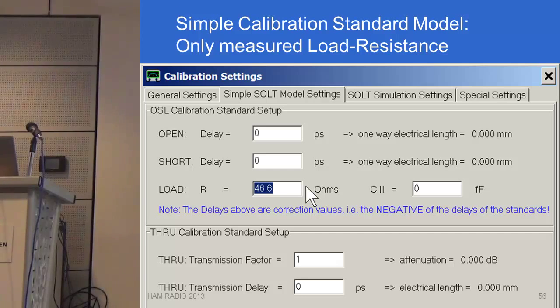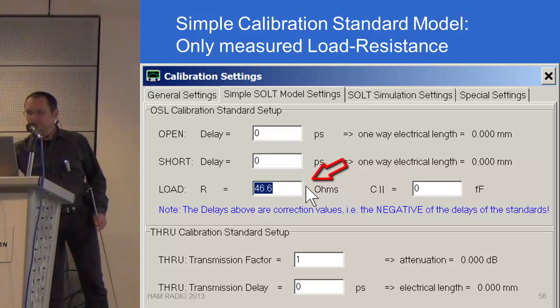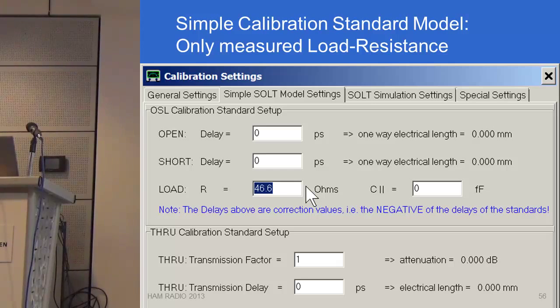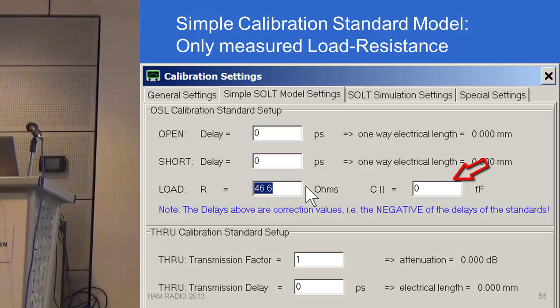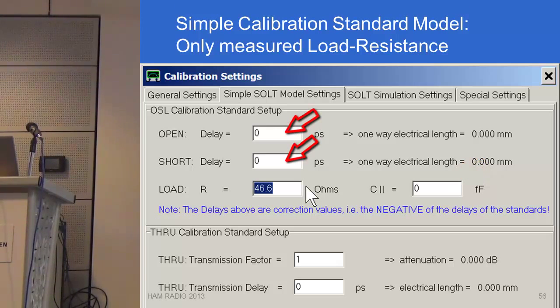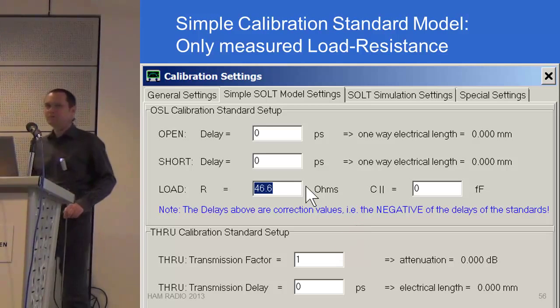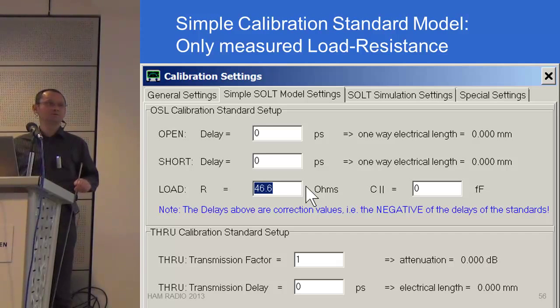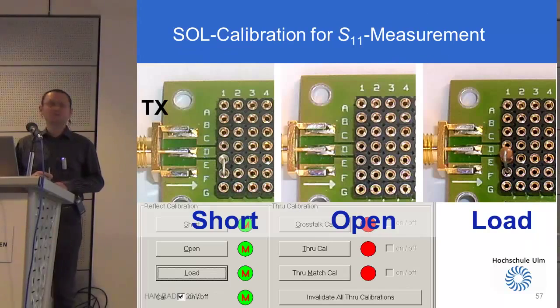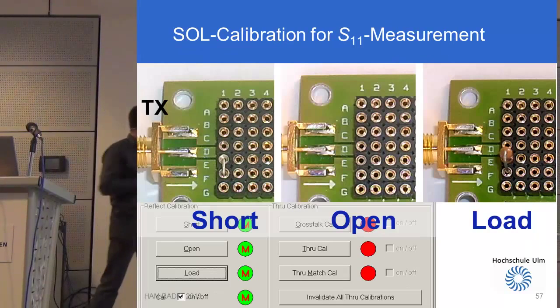Next step is to enter the parameters for the calibration standards, where the load resistance just measured is 46.6 ohm. The imaginary impedance at 10 MHz is only 0.01 ohm and can be disregarded, although some negative contribution should have been entered in the parallel C box. The open delay and short delay are entered as ideal 0 picoseconds as we do not know better. Likewise the through delay is set to 0 picoseconds, and as there is no loss, the transmission factor is set to 1. The few millimeter long through calibration standard is so short compared to the wavelength that it is regarded as negligible.